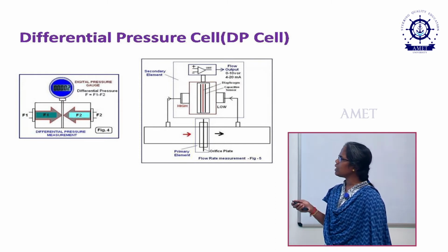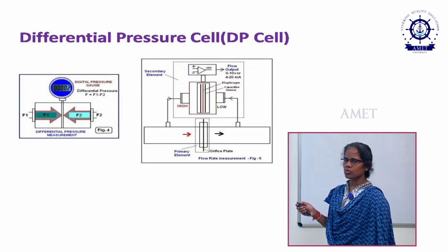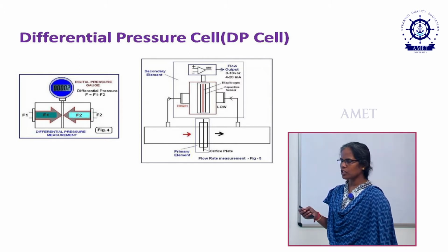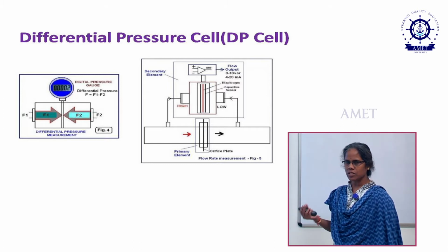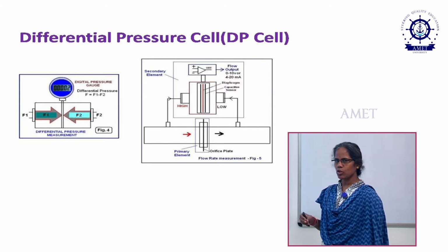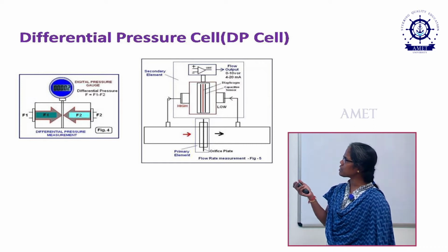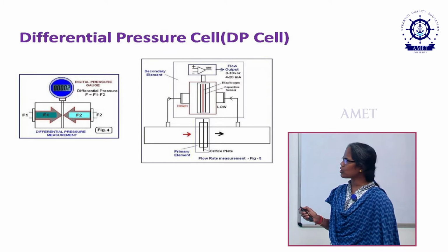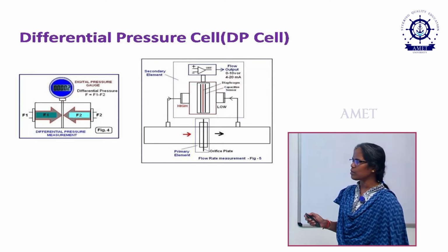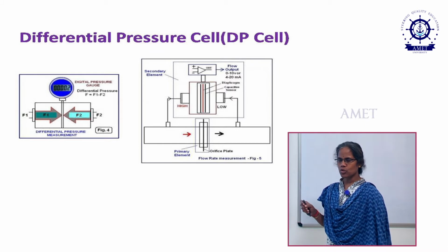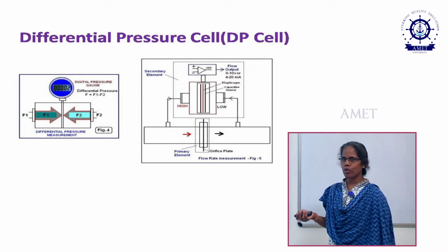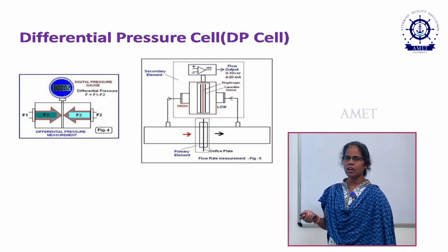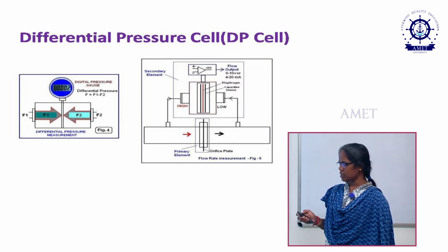It will be measured. Then there is the operational amplifier circuit. An operational amplifier converts a very small signal into a very high signal with high bandwidth. It has a very high input impedance and a low output impedance. The output is converted into 0 to 10 volts and 4 to 20 milliamps. This is used to control overflow or high error signals of the pressures using a PLC or SCADA or any other electrical signals.